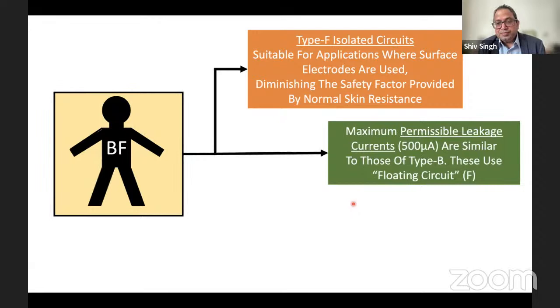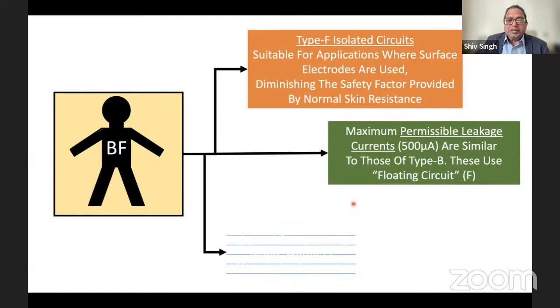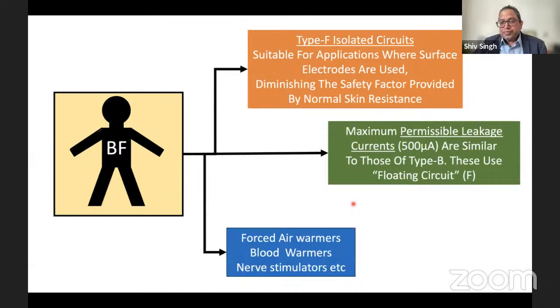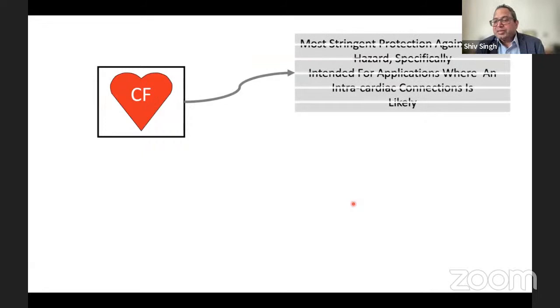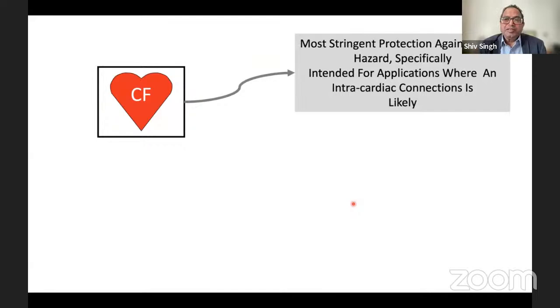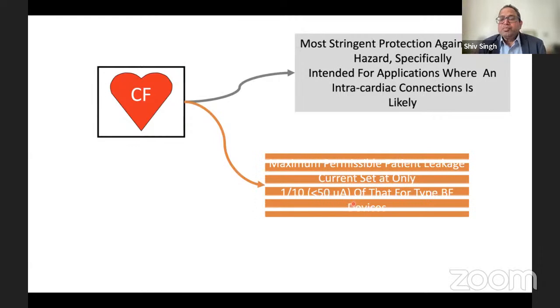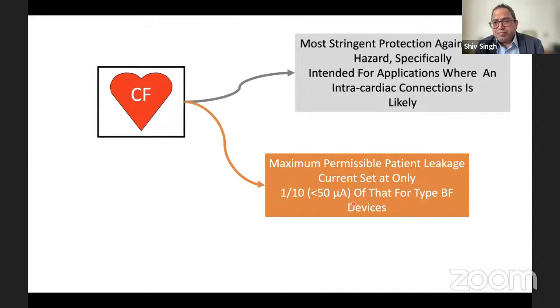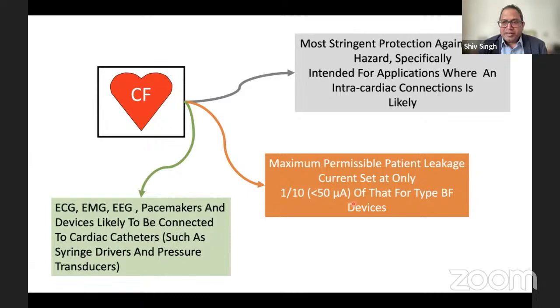That is type BF. Examples of these are your forced air warmers, blood warmers, and nerve stimulators. There's no type C because anything which is attached to the heart has to be very, very safe. So this is the most stringent protection against hazard, and it is intended for equipment which is applied with a direct intracardiac connection. Even though ECG does not actually have a direct connection, it is still type CF. But anything like an arterial line, central line, pulmonary artery flotation catheters, and pacing wires are all type CF. The maximum permissible leakage current in this case is 1/10 of type B or BF, so it's less than 50 microamps. And there will always be a floating circuit in these cases. So you're looking at ECG, EMG, EEG, pacemaker devices, and cardiac catheters of any kind, which have to be type CF.